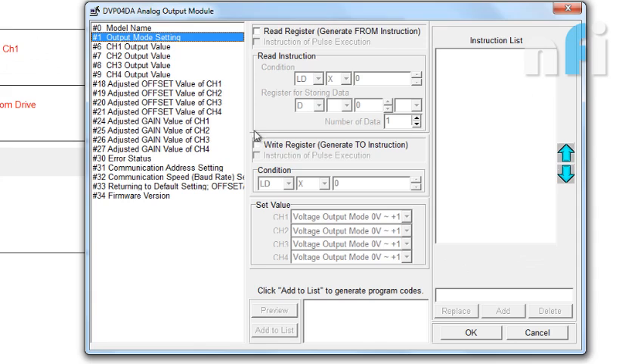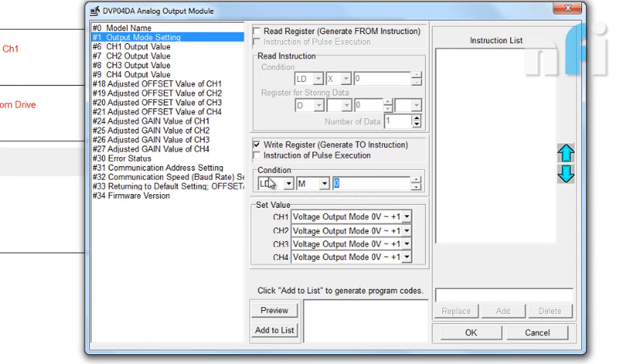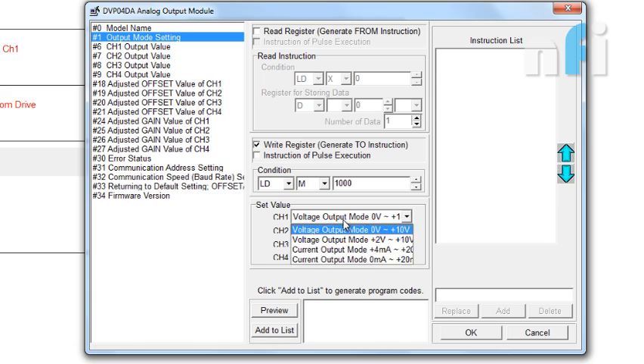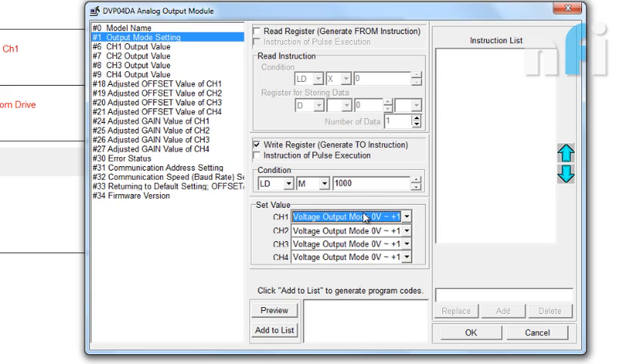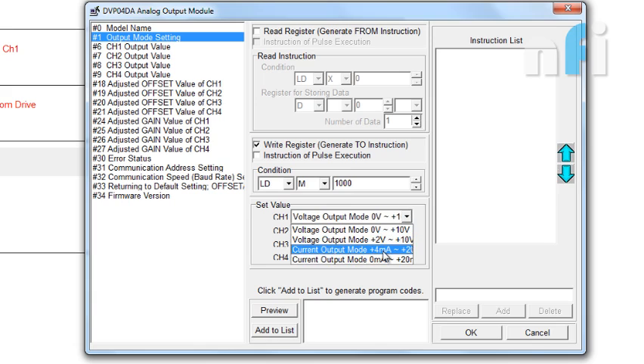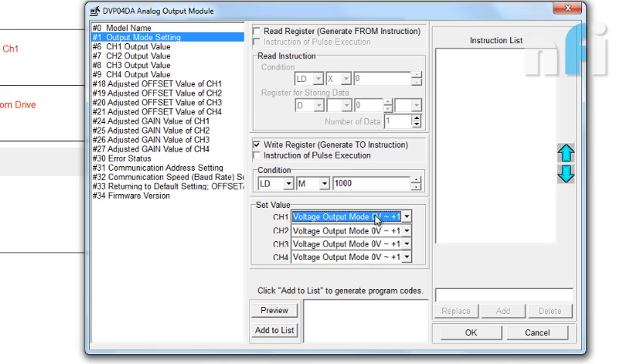Now the same situation - output mode settings. I want output in terms of voltage, so I am taking voltage output 0 to 10V. Similarly you can take current outputs. As my device is voltage operated because I am connecting this to AVI, I am using voltage output. If I would have been connecting to ACI, which is analog current input, I should have selected 4-20mA or 0-20mA.